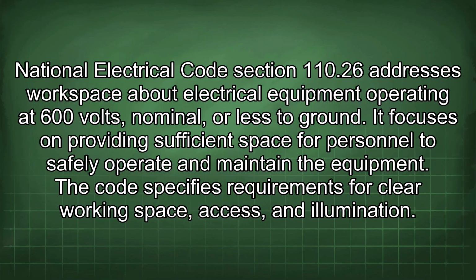National Electrical Code Section 110.26 addresses workspace about electrical equipment operating at 600 volts, nominal, or less to ground. It focuses on providing sufficient space for personnel to safely operate and maintain the equipment. The code specifies requirements for clear working space, access, and illumination.